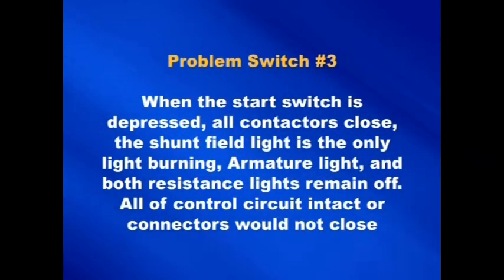Should the apprentice draw problem card number 3 for testing, it would read as follows. When the start switch is depressed, all contactors close. The shunt field light is the only light burning. The armature light and both resistance lights remain off. All of the control circuit is intact or the contactors would not close.